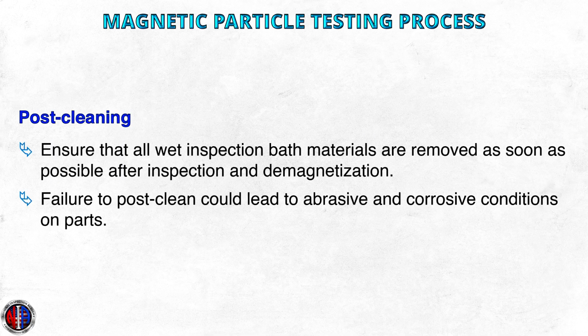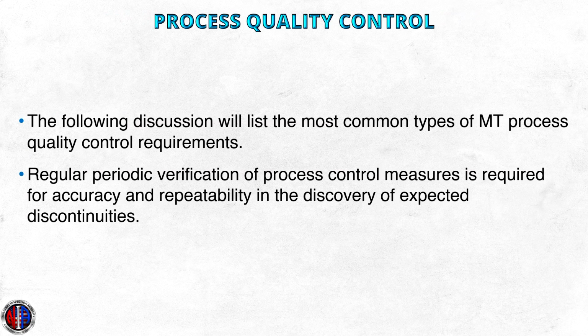Post-cleaning. To post-clean the test object, ensure that all wet inspection bath materials are removed as soon as possible after inspection and demagnetization. Failure to post-clean could lead to abrasive and corrosive conditions on the part. Process quality control. The following discussion will list the most common types of MT process quality control requirements. Regular periodic verification of process control measures is required for accuracy and repeatability in the discovery of expected discontinuities.